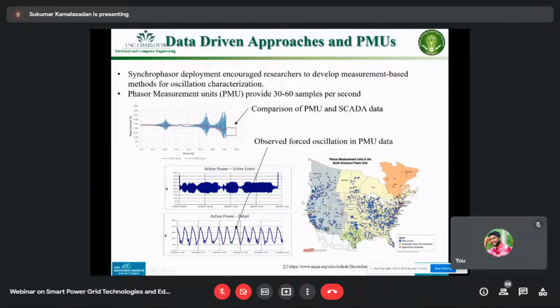The advantage of having these phasor measurement units is to see the data coming in. You can see the comparison of PMU and SCADA data. The blue ones show all the oscillations, but the phasor-related data coming from SCADA doesn't show any oscillations.